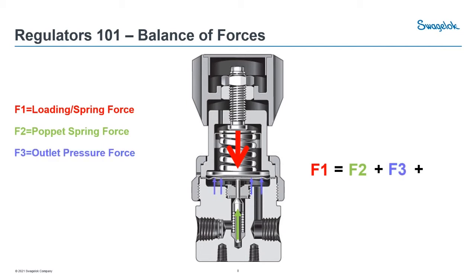Moving on, we have F3, our outlet pressure force — the force due to the pressure being exerted from your outlet pressure on the diaphragm or piston. And F4 is our inlet pressure force, being exerted on our poppet area from our inlet pressure. So we can see that the loading spring force is pretty much equal to our poppet, outlet, and inlet pressure forces combined.